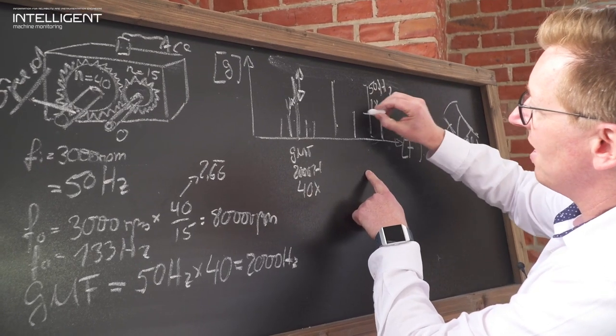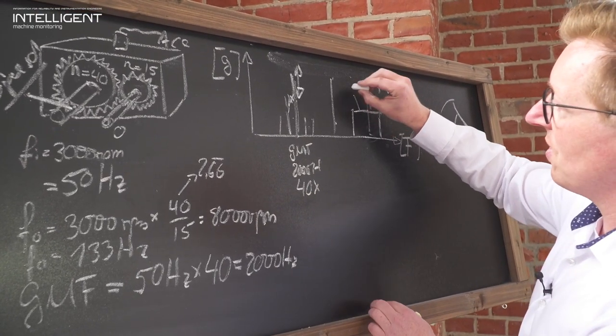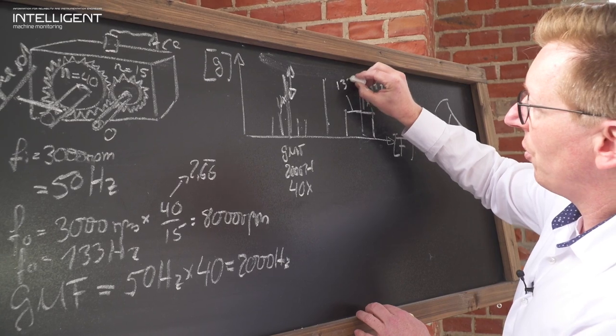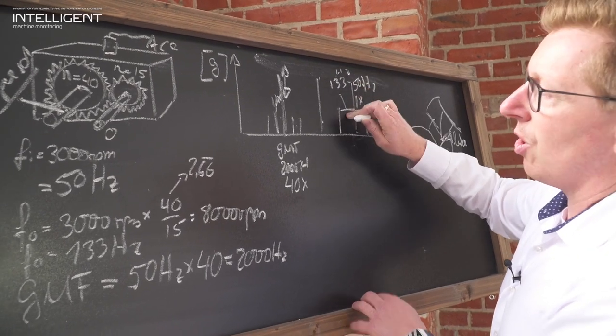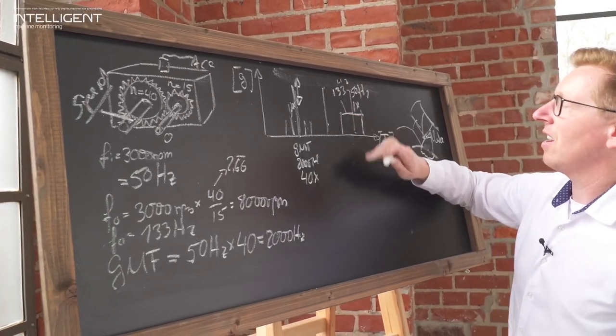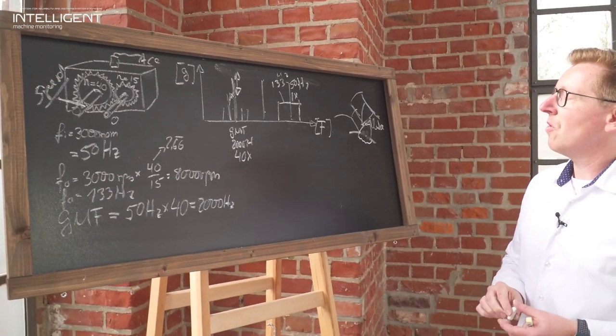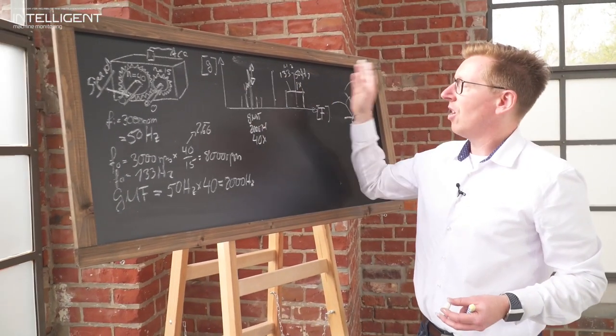or if the 1x is spaced at the larger frequency, say 133 Hertz, then it belongs to the pinion gear and would relate to a failure of the pinion gear from a spectrum perspective.